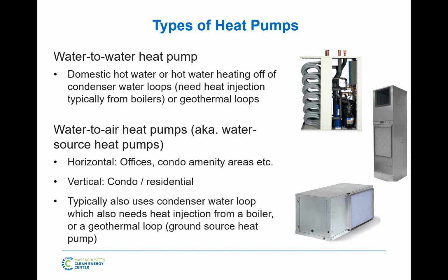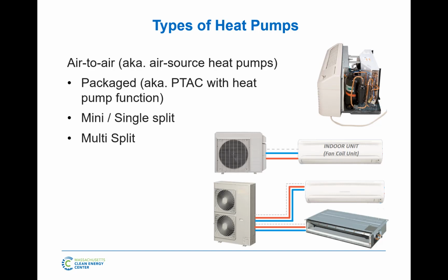But you can also connect these to a geothermal loop. So if a heat pump is connected to a geothermal loop, that's the name. We call them ground source heat pumps. So if you've heard of the term ground source heat pump, it's no different than a water source heat pump. Some of them have different ranges, maybe different compressors, but very similar concept. So with a geothermal loop, of course, that condenser water can get maintained either fully or partly using the ground loop.